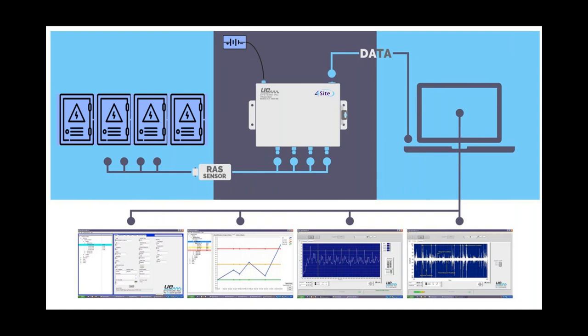Now what do we do with the Foresight? We've got this other product called the Foresight. It looks very much like the Forecast but is different internally — we listen at a different frequency to optimize it for electrical applications. Rather than attaching contact sensors to a bearing source, we have airborne sensors that we mount inside electrical gear. Those route back into the Foresight, we take the data into our computer, we can trend those readings and grab those sound files. As anybody that's done electrical inspections knows, those sound files are key for electricity — that is what we call the Foresight.